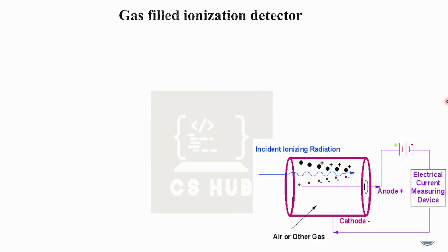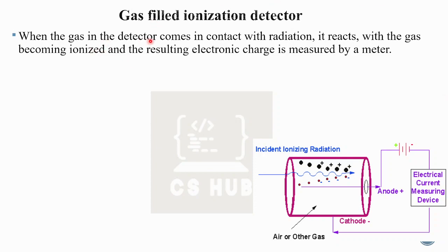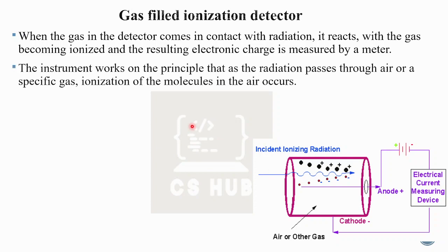The gas-filled ionization detector works as follows: when the gas in the detector comes in contact with radiation, it reacts with the gas, becoming ionized, and the resulting electronic charges are measured by a meter. The instrument works on the principle that as radiation passes through air or a specific gas, ionization of the molecules in the air occurs.